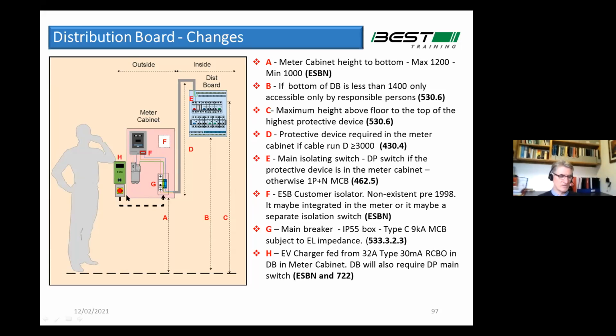The other thing I'm showing here that is under discussion at the moment is, again, the rollout of, we're trying to move towards electric vehicles. So they are going to allow the electric vehicle charger to be fed directly from the meter cabinet, which means now you're going to have to fit a main distribution board effectively in the meter cabinet, with an RCBO feeding your charger and a circuit breaker then feeding the board. That's the way it's going to go. So there's some of the things that are happening. These are not all necessarily IS 10101 requirements, but they're all tied in. Most of what you're looking at here are IS 10101 requirements.